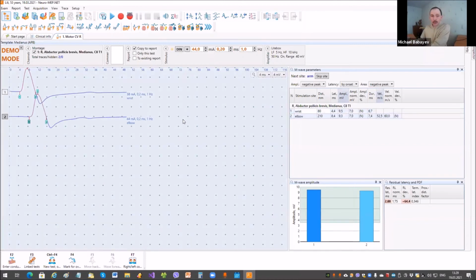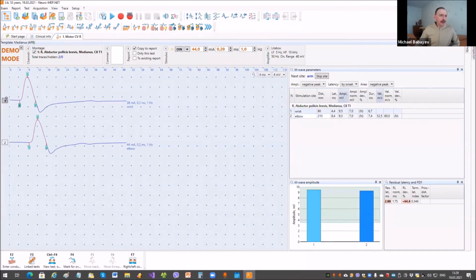OK, now we have two good responses, and you can see that all markers are placed automatically, but if you do not like the position, you can change it very easily with the mouse or from the device. Also, some parameters, amplitude, latencies, and velocities, are calculated automatically. Only for velocity, you have to check the distance. By default, we have one, but it is necessary to measure and input the real distance.